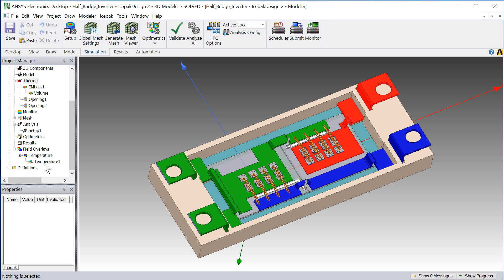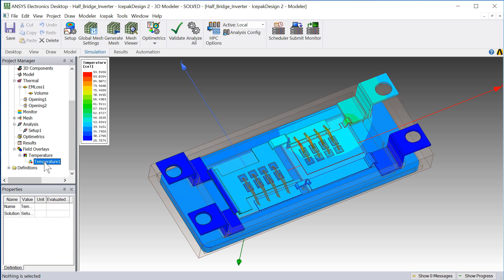Once the simulation ends, we can generate the temperature plot. The maximum junction temperatures are much lower now. They are 93.5 degrees centigrade. That's 21 degrees lower than the original.